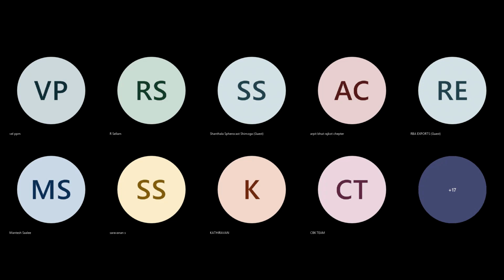So 3190 liters, which is 112.64 cubic feet. Okay. Then the load pressure is 6 bar. Then unload pressure is 7 bar. The difference between load pressure and unload pressure is 1 bar. So is what we see. So atmospheric pressure is again 0.97 because 1.03 bar is atmospheric pressure. So that is why 1 bar gauge pressure is converted to 0.97 atmosphere is what it means. Then time taken to unload is 6.6 seconds.